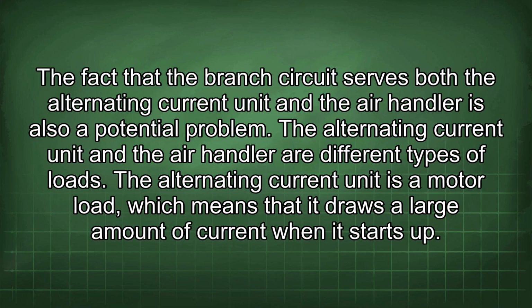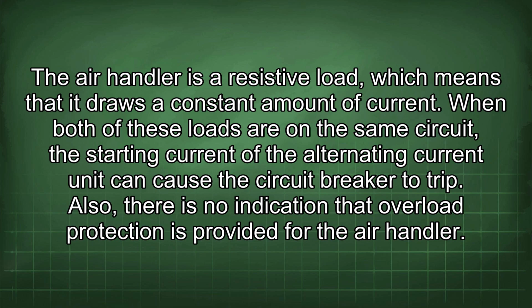The fact that the branch circuit serves both the alternating current unit and the air handler is also a potential problem. The alternating current unit and the air handler are different types of loads. The alternating current unit is a motor load, which means that it draws a large amount of current when it starts up. The air handler is a resistive load, which means that it draws a constant amount of current. When both of these loads are on the same circuit, the starting current of the alternating current unit can cause the circuit breaker to trip.